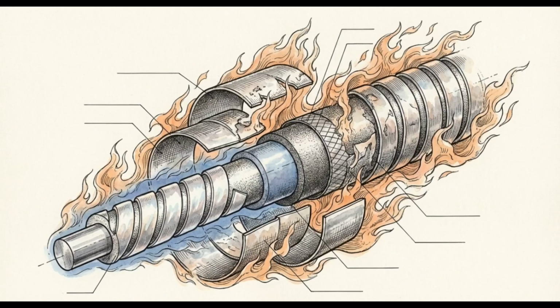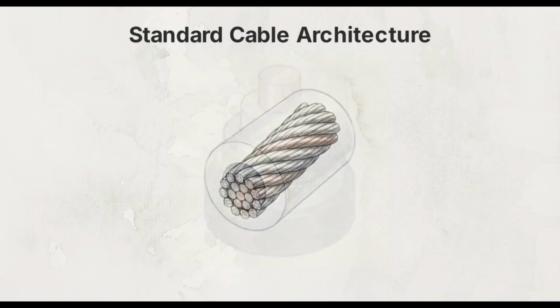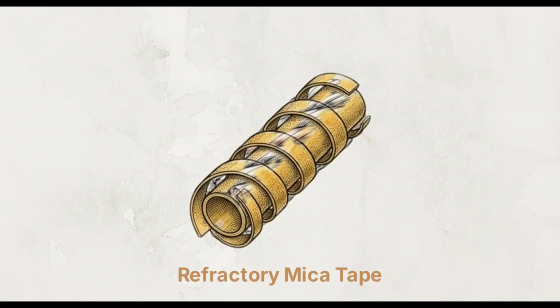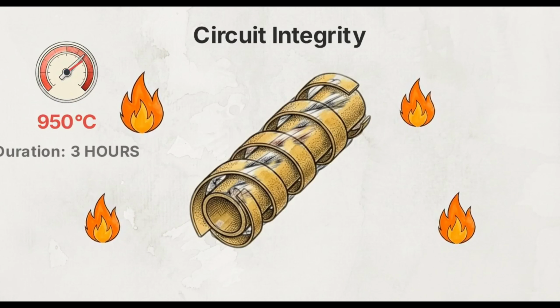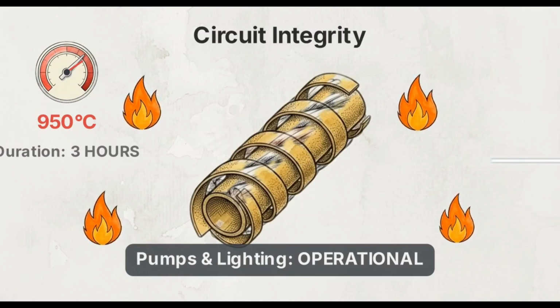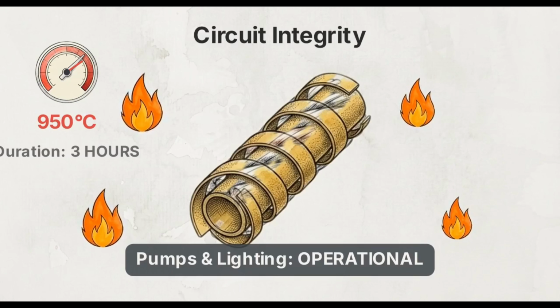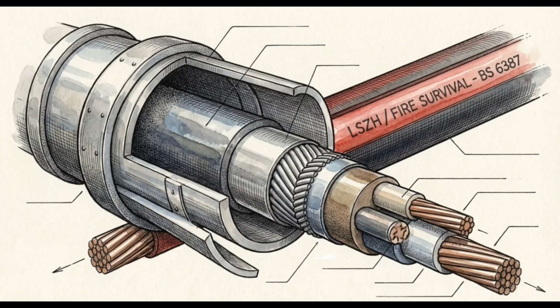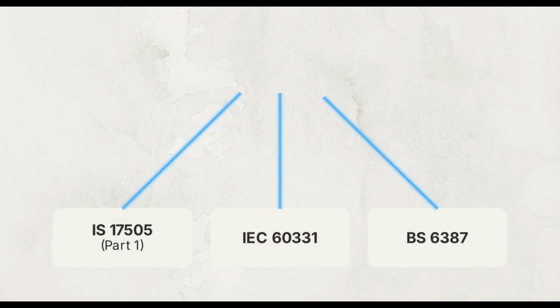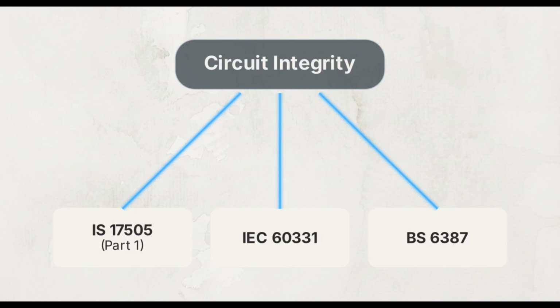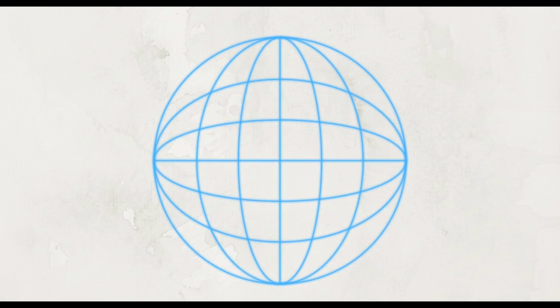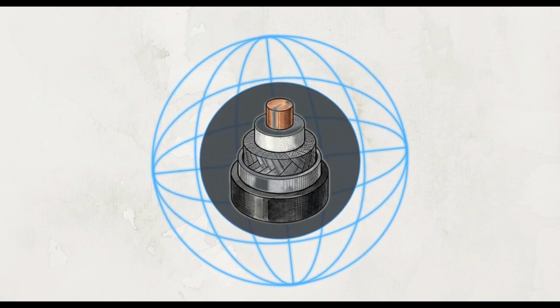The Fire Survival Standard shifts the engineering objective toward ensuring active operational endurance during an ongoing structural fire. This standard relies on a hidden mechanism, refractory mica tape wrapped directly around the raw copper conductor. This unyielding layer must maintain circuit integrity for 3 hours at 950 degrees Celsius, ensuring critical fire pumps and lighting remain operational while the building burns. Modern outer sheathing functions as a heavily regulated life safety technology built to satisfy the uncompromising requirements of global fire codes. This matrix shows the interlocking complexity of international regulations, where national frameworks are increasingly forced into alignment with apex global safety standards. This harmonization reflects a permanent global transition towards thermosetting polymers and more rigorous safety benchmarks in high-density infrastructure.